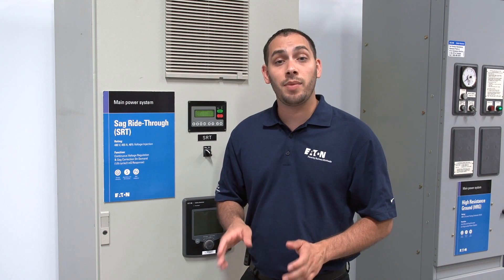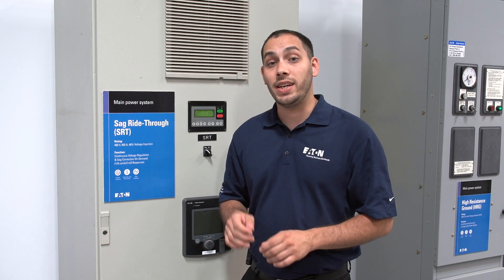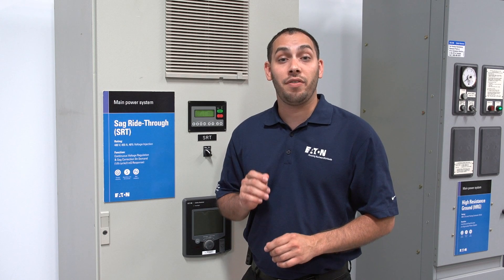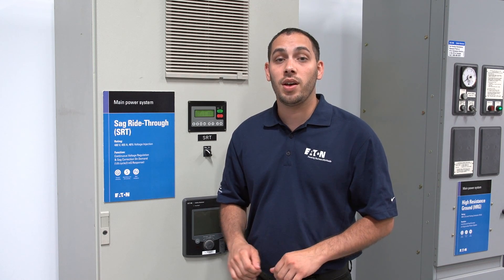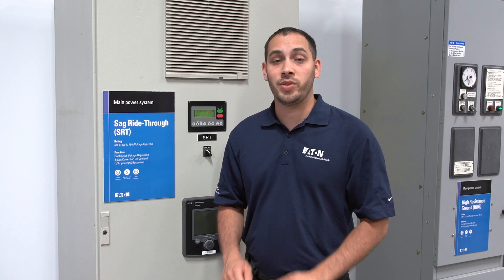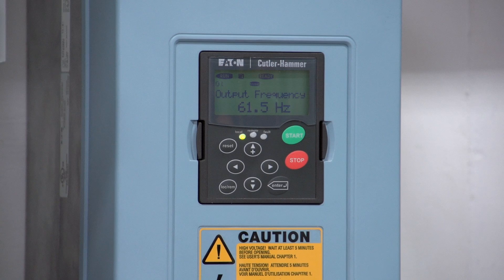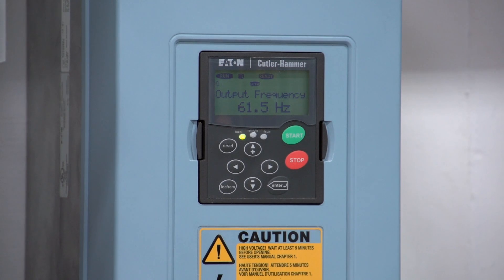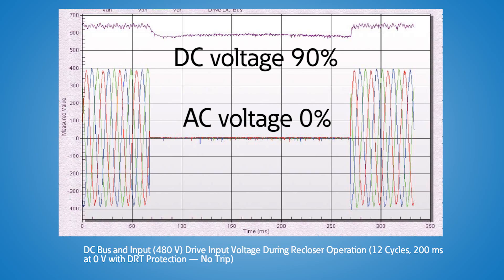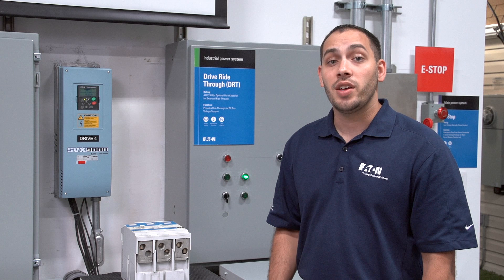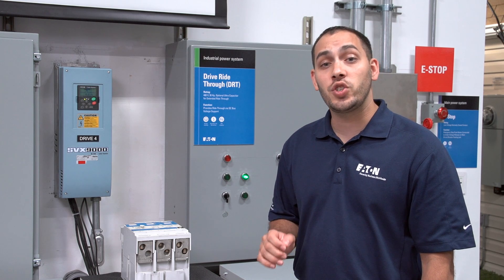However, sometimes you may only need to protect a few or a single critical load, like a variable frequency drive. A drive ride-through is used to maintain a constant DC bus voltage on a variable frequency drive during a sag event. They can also be outfitted with ultra-capacitors to ride through short-term full interruptions.